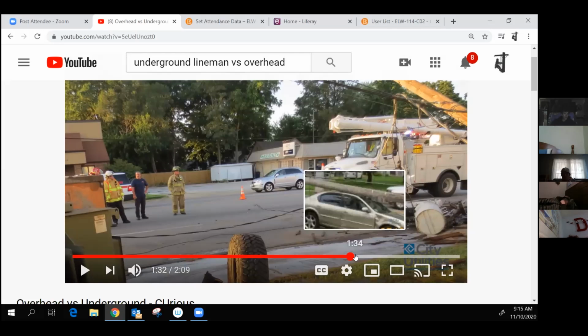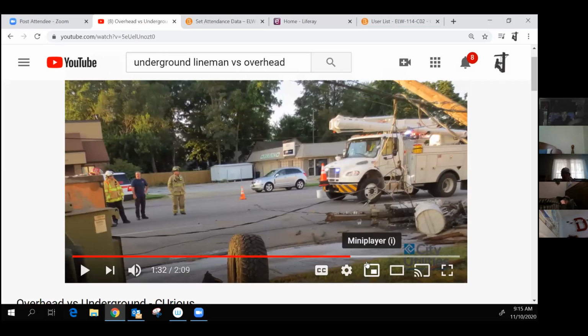Yeah. I mean, you got a pole sitting right there, wires on the ground and everything. Everything's exposed and just really ready to be put back. You put that new pole in the ground, you hang a new transformer, you just pull everything back to the pole. If you need to do splicing, you need to do that, and you just reconnect. Go to the underground one, Robbie. Okay. The mess. Yeah.